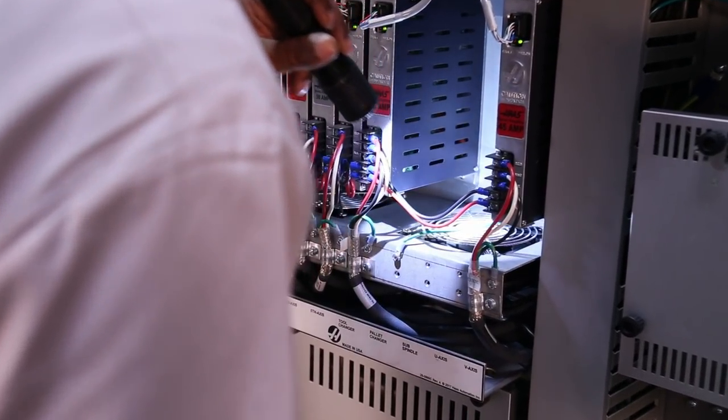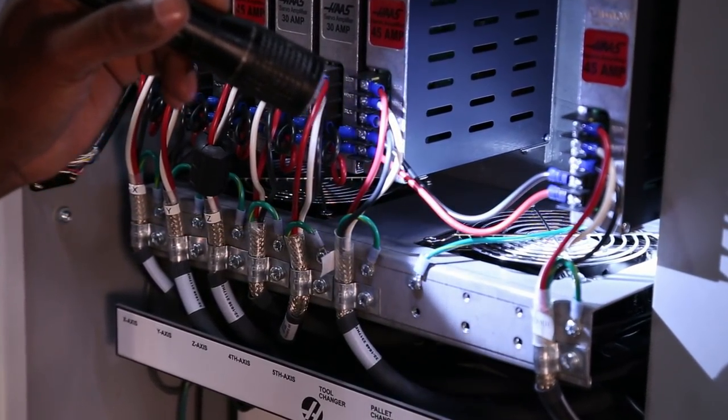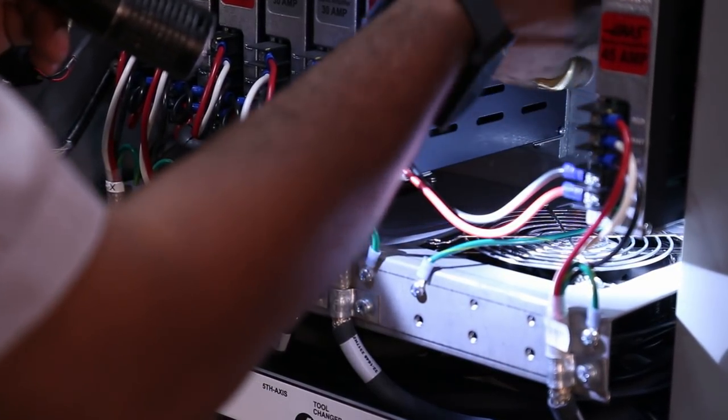Make sure the fans below the amplifiers inside the control are working correctly. They are designed to pull fresh air up from beneath the machine and cool the amplifiers.